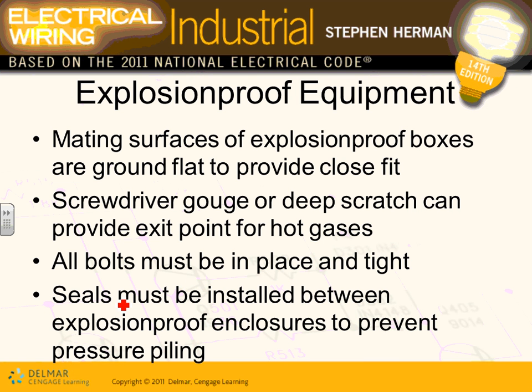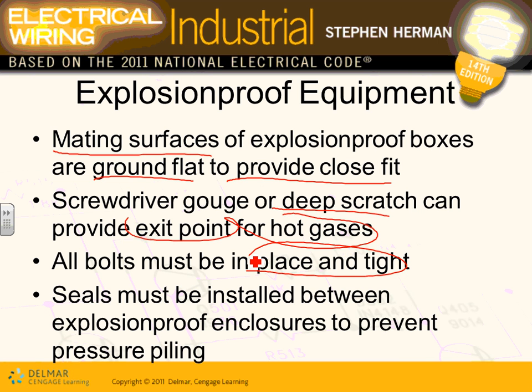Okay, a couple of things about explosion-proof equipment, guys. When they tie them together, they bolt them. I'll show you. They're bolted together. The mating surfaces of the explosion-proof boxes are ground flat to provide a close fitting, so you can't just go and scratch that mating surface. If you scratch it, you will alter the characteristic of that surface, and basically you disable it. Screwdrivers, gouges, or deep scratches will provide an exit point for the hot gases, so you don't want to do that. All bolts must be placed and tightened. There's tons of bolts that have to be tightened.